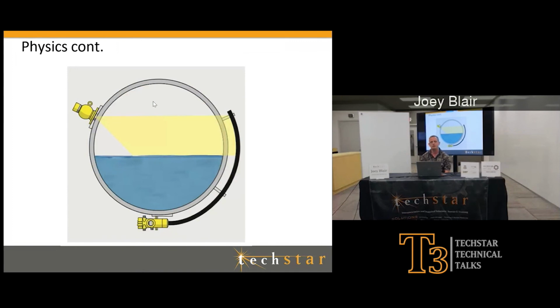So here's just another picture of a way a vessel might be. We have collimation angles, which is that beam, if you look at how it goes across. What you have is a small pill inside of your source. That's where the radiation is. It's the cesium-137, and that entire big source holder is nothing but lead. Okay, and it only lets the radiation beam pass out in the angle that we want it to pass out. So it has a 45-degree angle cut into it, and radiation is painting a small portion of your vessel, maybe about a foot or two, maybe about a foot's area on the other side of the vessel with radiation.